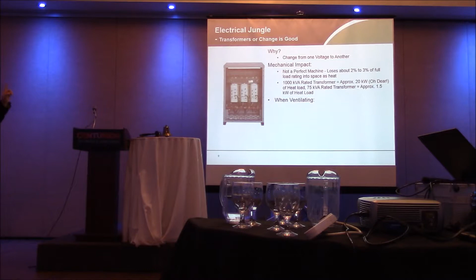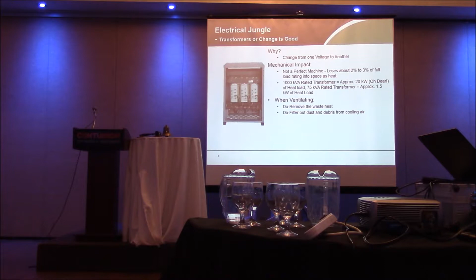My favorite is when they ventilate the transformer that's in the electrical room next to the parking garage, and they pull the air out of the parking garage, which is full of car exhaust, dust, dirt and salt. You should see what it does to the inside of the transformer, with all that moisture coming off the cars blowing through there. So if the electrical room's next to a parking garage, pull the air from someplace else and blow it into the parking garage - the warm air coming out will warm up the parking garage, so you're getting free heat. But don't do it the other way around.